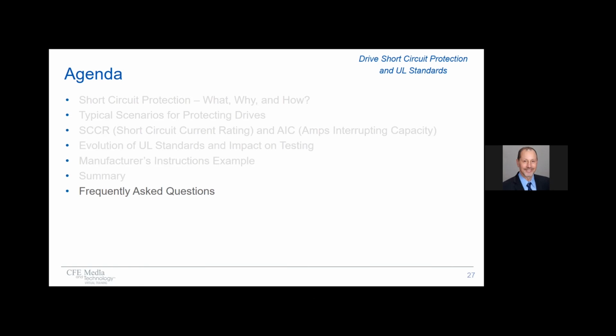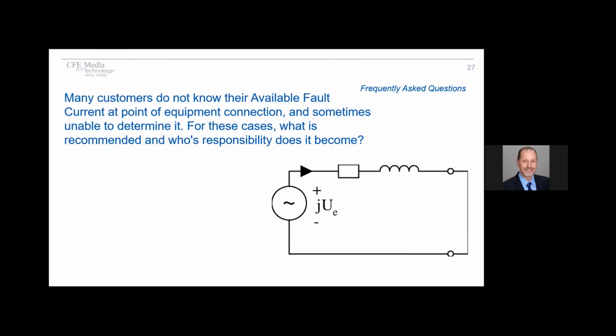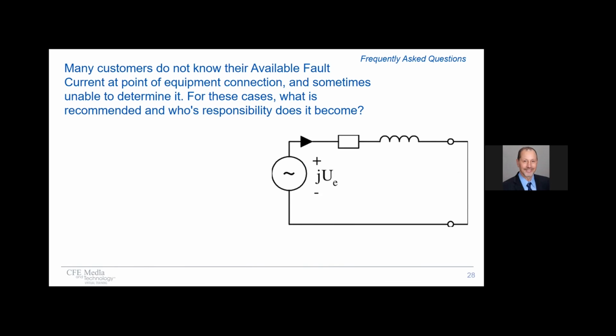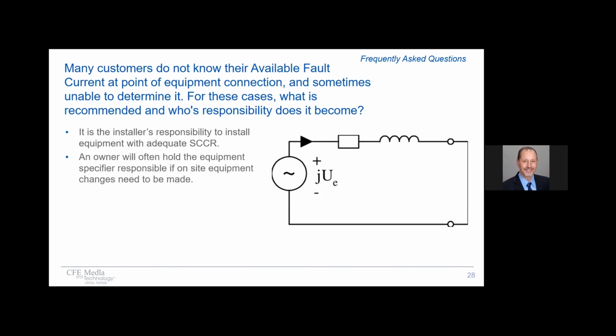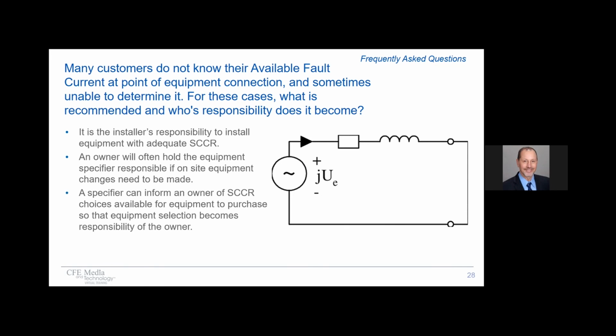That nearly completes our presentation today. Before I hand it back to Kevin for open Q&A, I'm going to address a few common questions. First of all, question number one: many customers do not know their available fault current at a point of equipment connection and sometimes are unable to determine it. For these cases, what is recommended and whose responsibility does it become? Well, it is the installer's responsibility to install equipment with adequate withstand rating. And an owner will often hold the equipment specifier responsible if on-site equipment changes need to be made. But a specifier can inform an owner of withstand choices that are available for equipment to purchase, so that then the equipment selection becomes the responsibility of the owner.